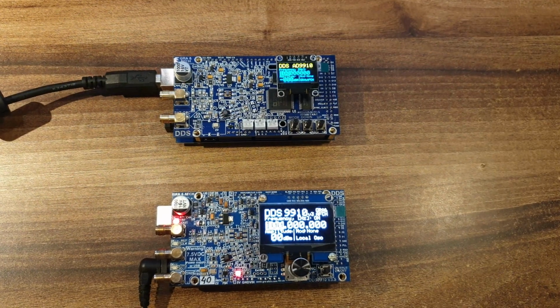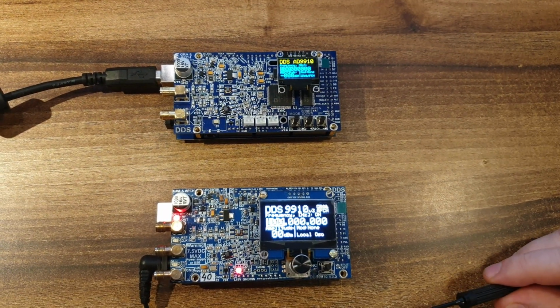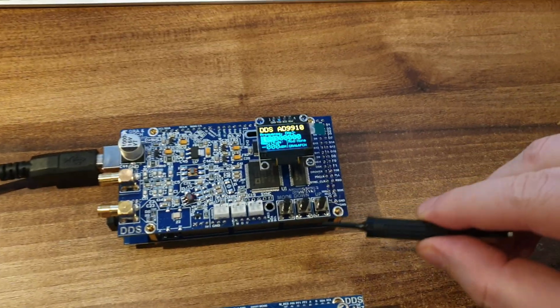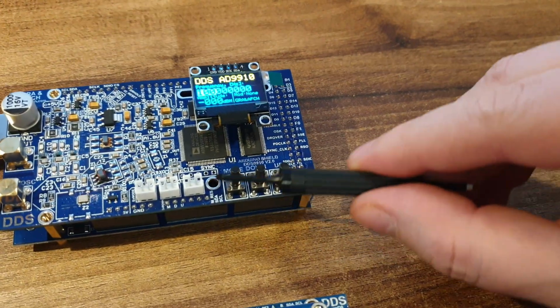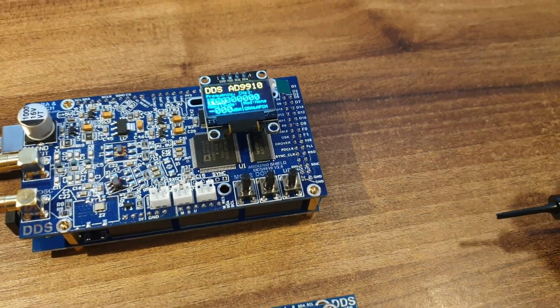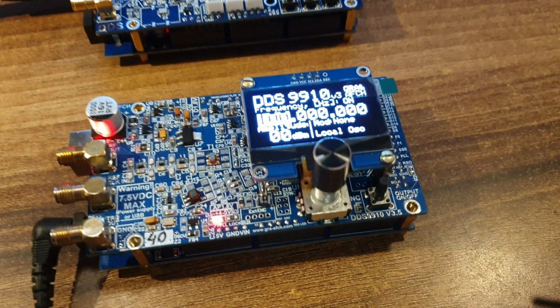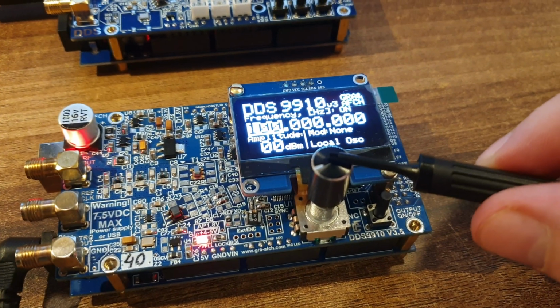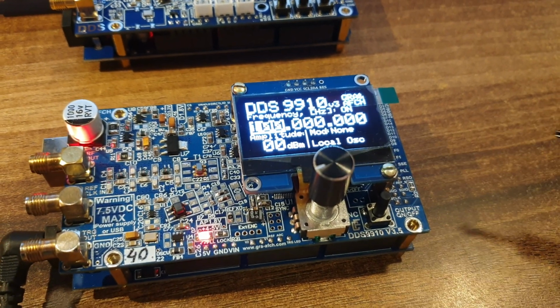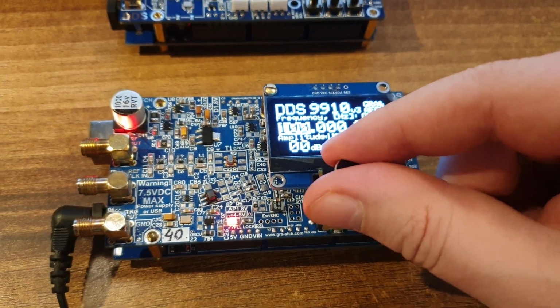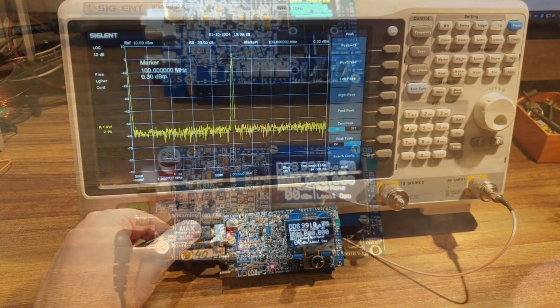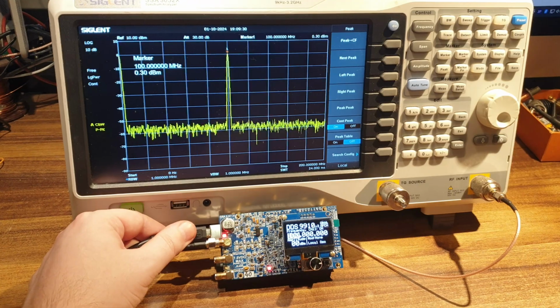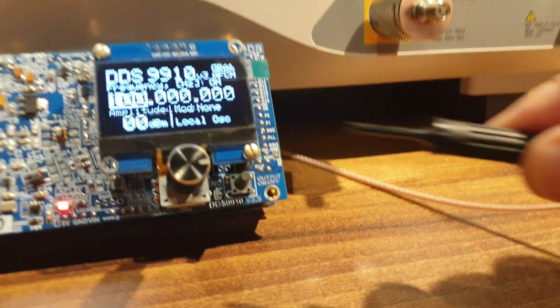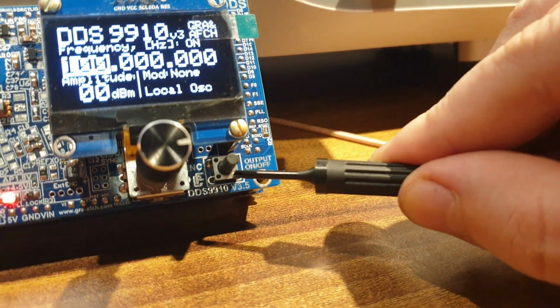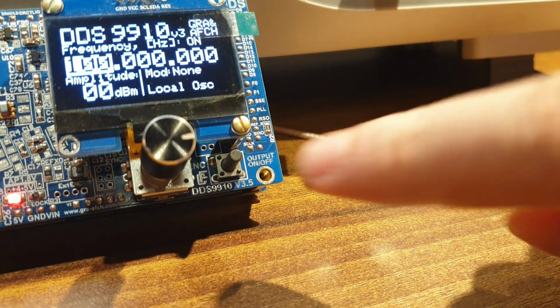Now, let's discuss each innovation in more detail. In the old version, three buttons were used for control and navigation through the menu, while in the new version, they have been replaced with a convenient encoder that allows for quick adjustments of parameters across a wide range of values. Another modification was the addition of a dedicated button for quickly enabling or disabling the signal on the RF output.